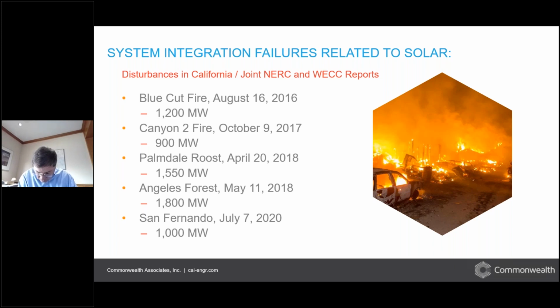One key type of commonality between these different incidents is momentary cessation. That's a common denominator in a lot of these: the inverter output just stopped, because a control function was improperly set at the beginning, just a default of the manufacturer, so that when they see a hiccup on the system, the inverter output is just going to shut off.